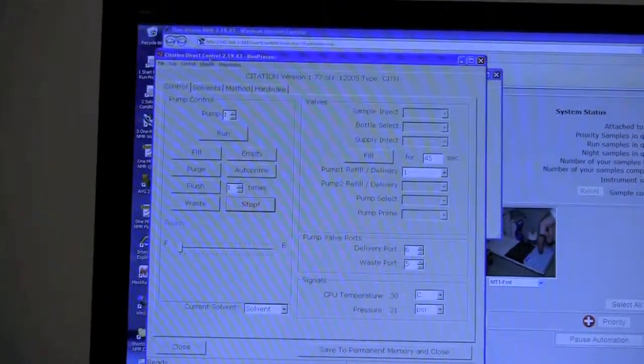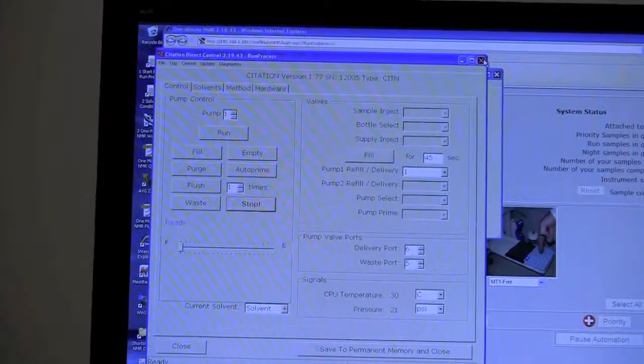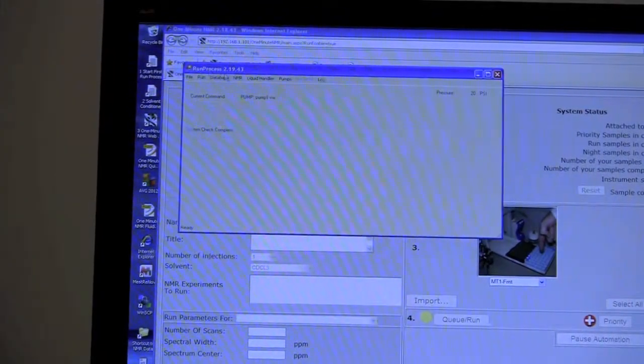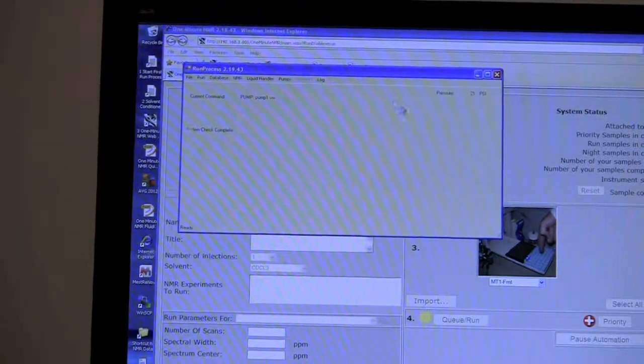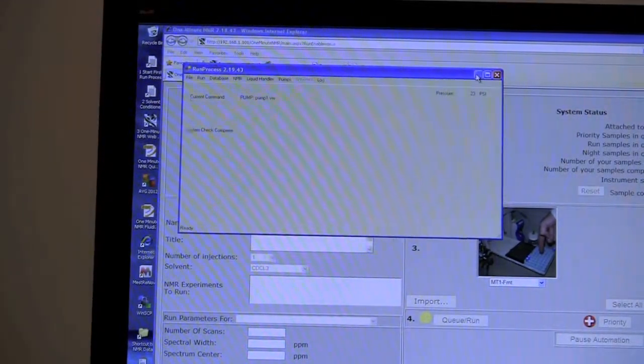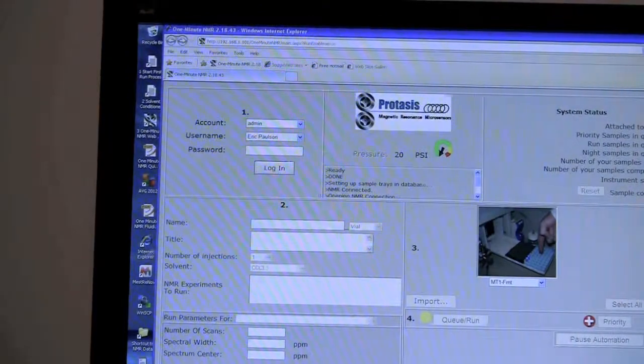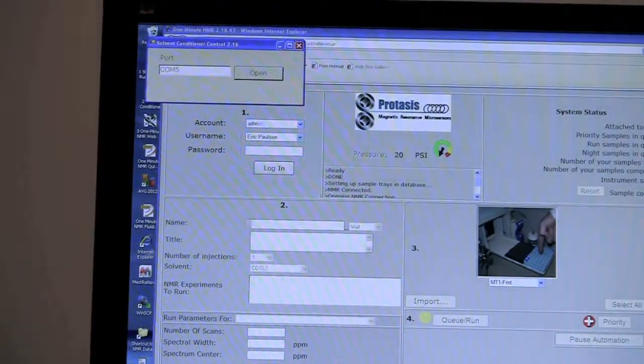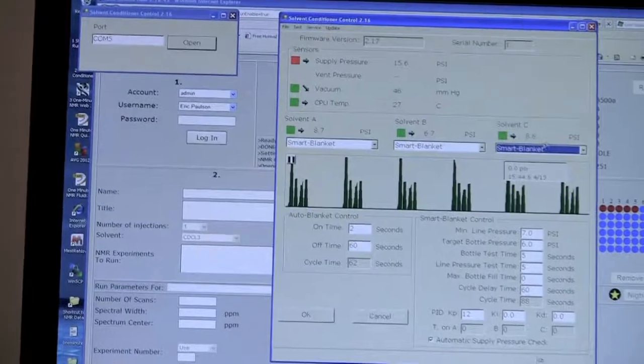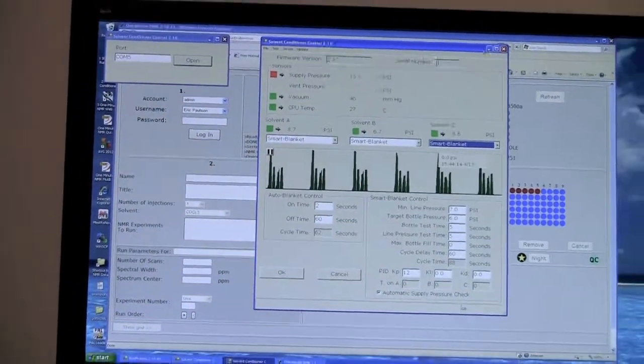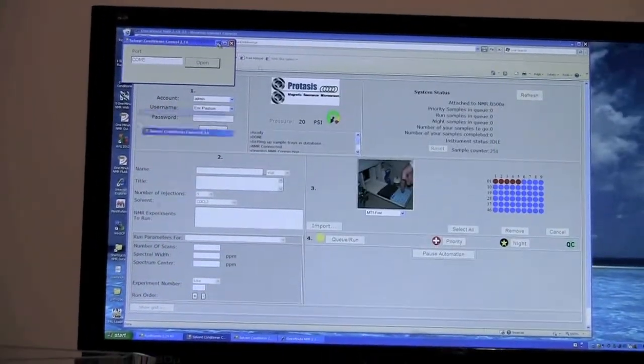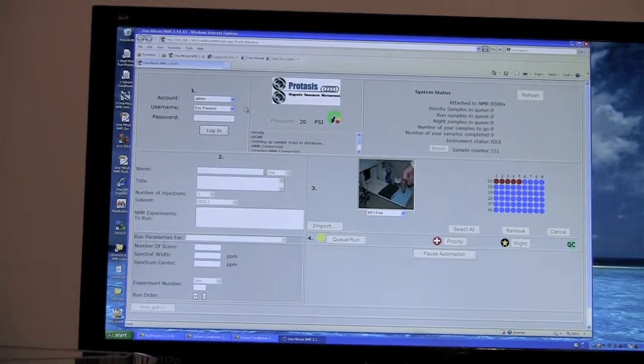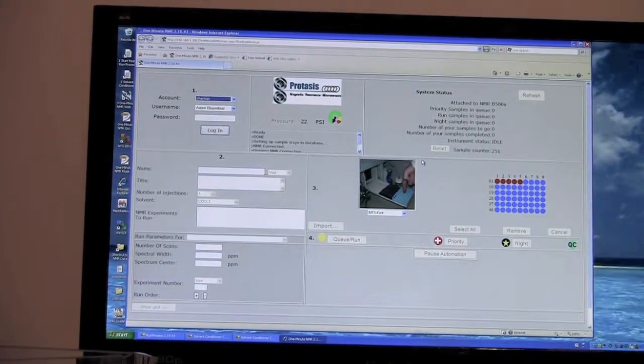You can close this direct control window, but you should leave this Run Process window open. If you close that, it will lose communication with the automation system. So leave that open, just minimize it. And then make sure that the solvent conditioner is running. That puts a blanket of nitrogen over the solvent, so that should be running in the background. And then the web page should be available here for somebody to log in. Now it's ready to go, and the next person can use it for automation.